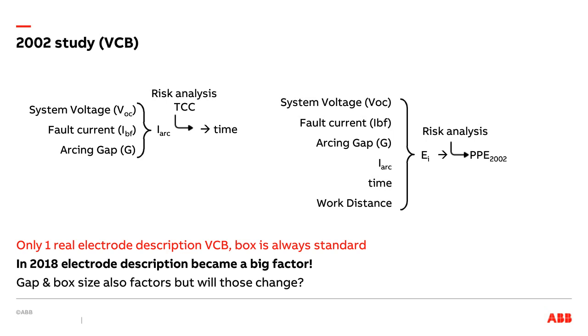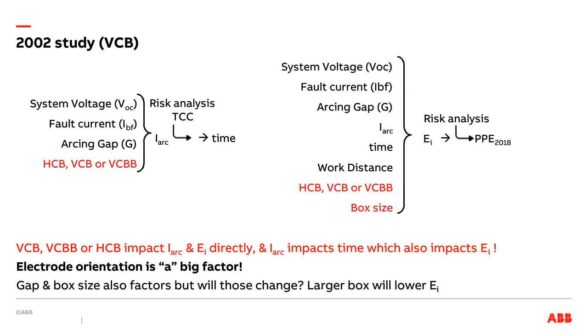In the new method, you'll have to add that as a variable. And that ends up being a big variable. Box size is also a variable in the energy calculation. And again, in my experience, most people are not fooling around with that variable, and they're kind of using the suggested values, the standard values, most of the time. Not saying that that's wrong or right. That simply seems to be what most people are doing. Me personally, I think I have an issue when the boxes are very, very, very big, and what that does to arcing current. Well, that's a different conversation for another day.